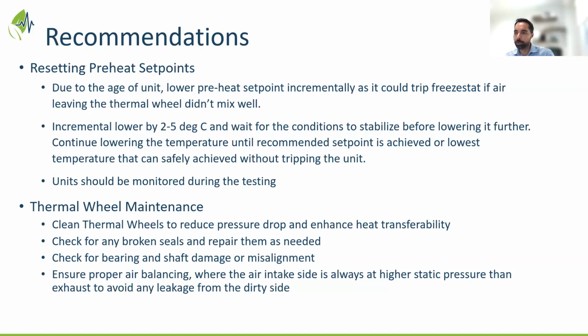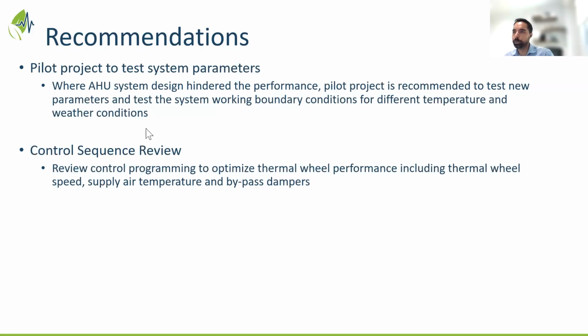Thermal wheel maintenance, as we talked about, is also important. So, regular checkups, making sure your air balance is there, making sure bearings and shafts are not damaged or misaligned, and that your media is still recovering the heat that's needed to put back into the system. We also talked about a couple of pilot projects that are initiating to mitigate or understand the existing inefficiencies in the current design, and where the boundary is for your system to operate within those current design features. Because it's hard to change the existing design, it's a lot of capital, but there's still opportunity to use technology to make the system work.